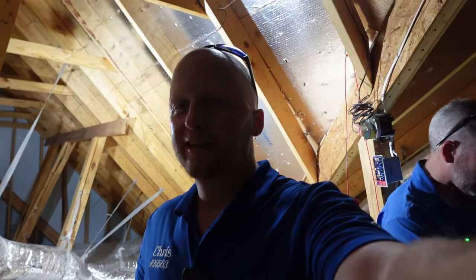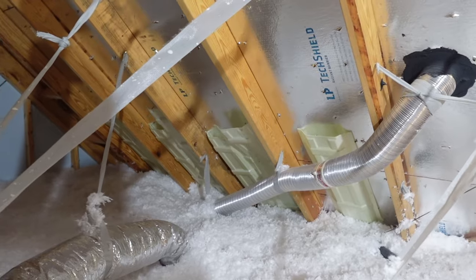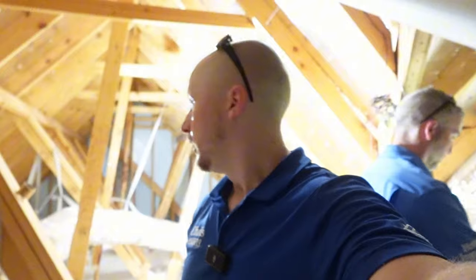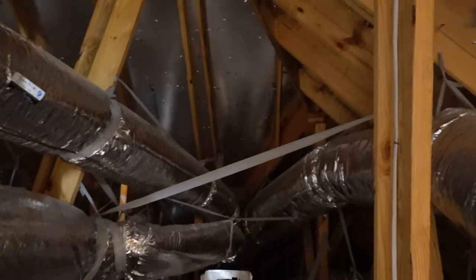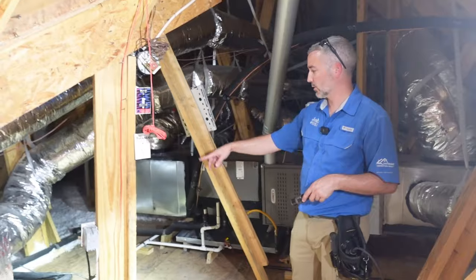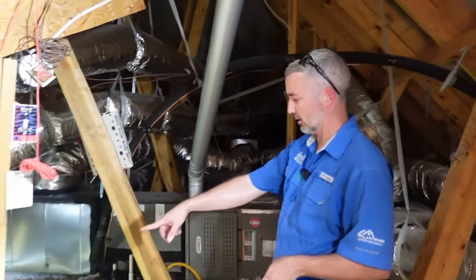Moving into the attic space — this attic space is looking pretty good so far. There's a good amount of insulation, a lot of baffles providing good airflow, and the ridge vent is open. We have airflow coming from the soffits all the way up to the ridge vent. All the mechanical exhaust vents are going outside and are sealed up really well. All the ductwork is lifted, suspended, and separated — some really good stuff in this attic space. But Josh did find one thing — we always find something. We have an Aprilaire dehumidifier installed.